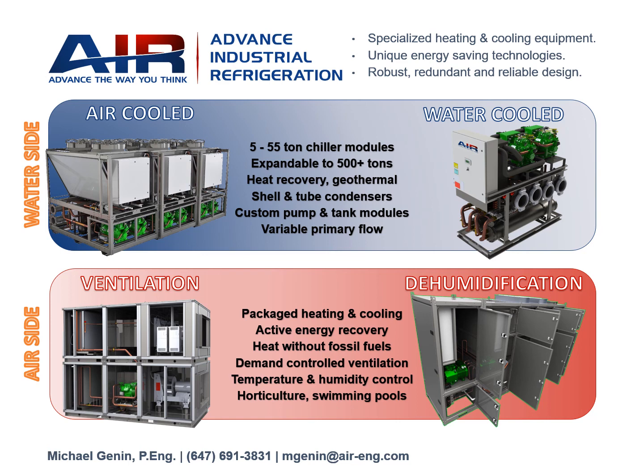And another question is, can the unit be placed outdoors? And the answer is absolutely. The majority of these units are designed to go outdoors and be weatherproof. They are available, like in the photo on the screen, in a stacked configuration. Typically those are for indoor use. They just show better on the presentation. And also in a side-by-side airflow configuration that's typically better suited for outdoors where you have more space and it's easier to service that way. So they're available in both configurations.